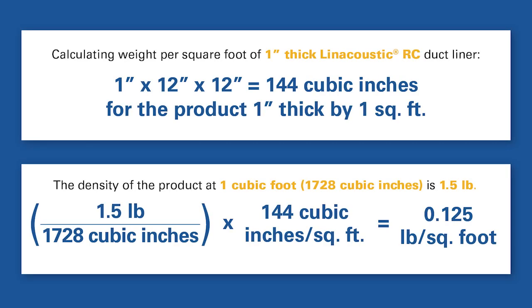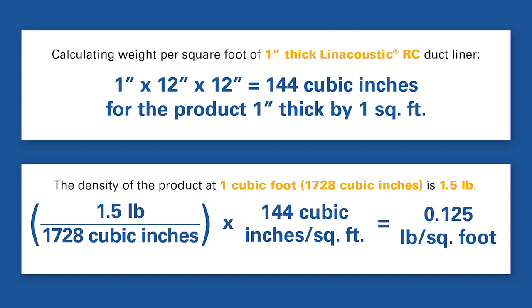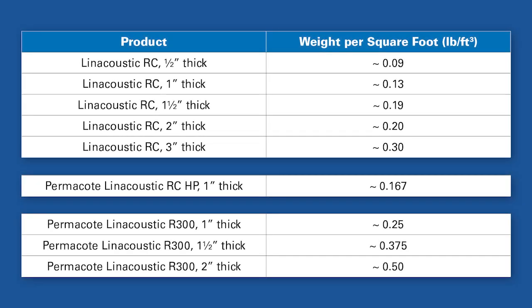First, you're going to take that one and a half pounds per cubic foot and then divide it by 1728 cubic inches per cubic foot — that's a conversion factor so we can get the math to work out. Next, we want to know what just this one section is, and this one section has 144 cubic inches for the one square foot of material. So we're going to multiply by 144 cubic inches divided by feet squared. That's going to result in 0.125 pounds per square foot of one inch duct liner. In front of you, you can see a chart that shows the weight per square foot of a variety of our Linacoustic products, so you can use them when designing your engineering system.